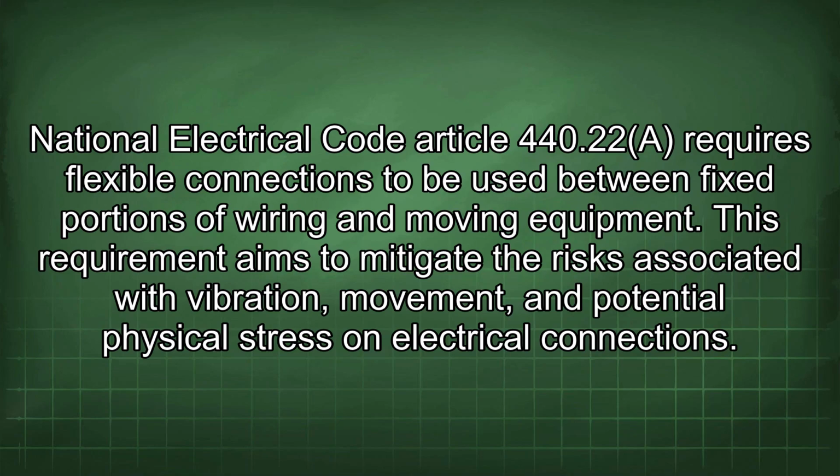National Electrical Code Article 440.22 requires flexible connections to be used between fixed portions of wiring and moving equipment. This requirement aims to mitigate the risks associated with vibration, movement, and potential physical stress on electrical connections.